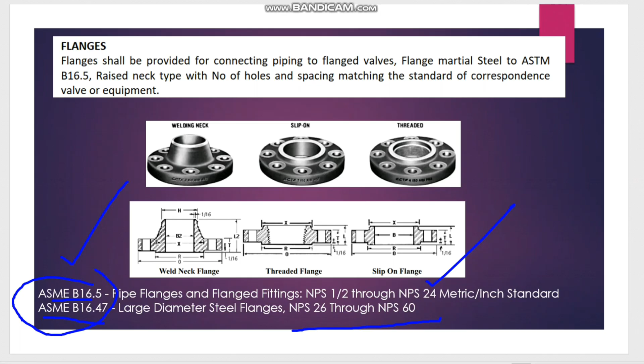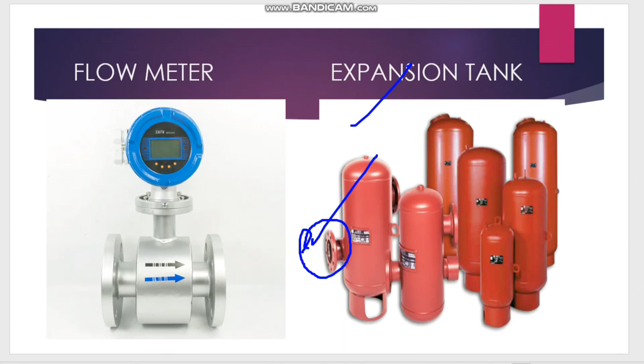This is mostly asked in interviews on the piping side. And here we have to make sure the flanges of the flow meter as well as the piping flanges are matching, because sometimes we get the flow meter from European countries, so they will follow the British standard, and we get the flanges from American countries, so they will follow the American standard. So both will not match, and we have to make sure both have the proper connection when it comes to the order. Like you see here, the expansion tank will have the flange connection. The expansion tank, air separator, and all the accessories in the ETS room and chilled water system mostly have flange connections. We have to make sure this point is properly considered.